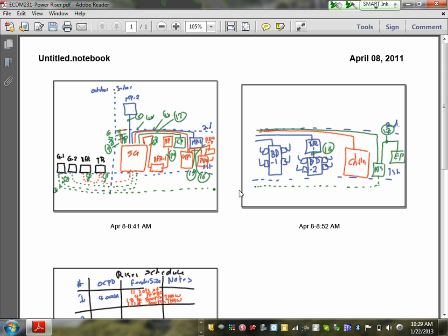But there's two different ways. Open transition means you basically shut the generators off and then you close the utility. Well, then you get a bump going back the other way, a blip. You lose power for a certain amount of time. And then the closed transition is what I was talking about. We're watching the generators while they're out of sync. And then all of a sudden, there's a point where the waveforms are in sync. We'll close the utility. So now we're on utility power, and then we'll take the generators offline, and we haven't lost power to the customer. The customer has no idea. So that's the difference between open and closed transition.